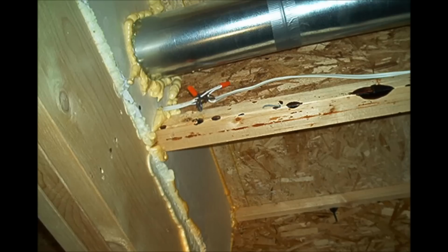Unusual efforts to seal the basement grow area from the upstairs living area are seen here. The drywall and spray foam between the floor joists is a definite red flag. You can also see some bad wiring conditions here, which are likely the result of removing some wiring for grow lights. Here you can see the return air duct is blocked off in the living area. Flex ducting is often run from the basement to the attic and connected to an existing or second chimney that has been installed. This charcoal filter was used to deodorize the air before exhausting it outside through the chimney.